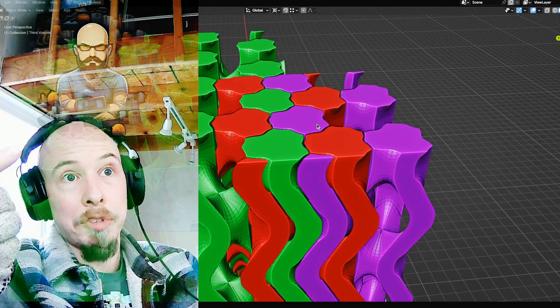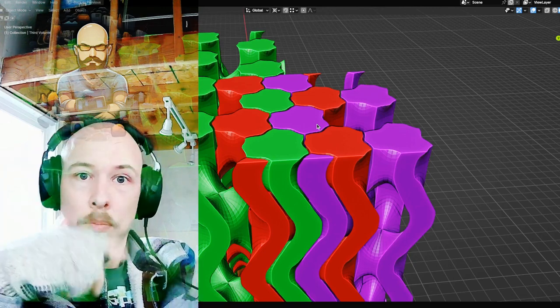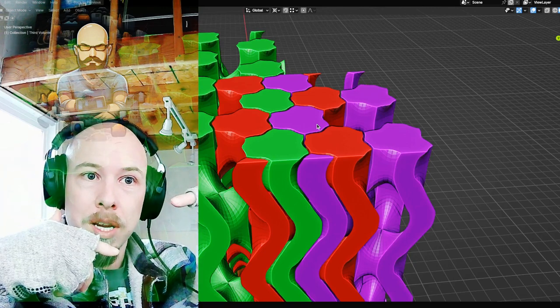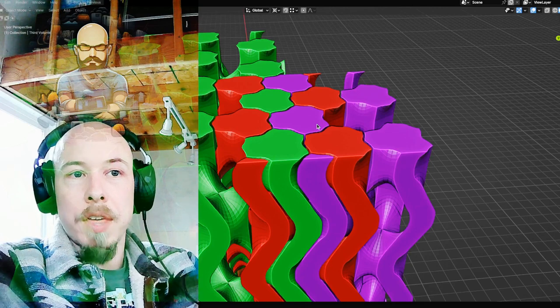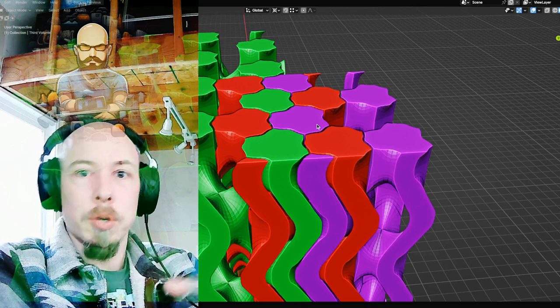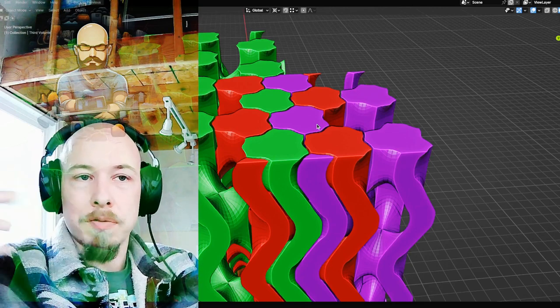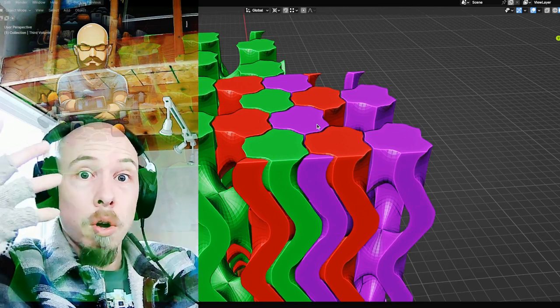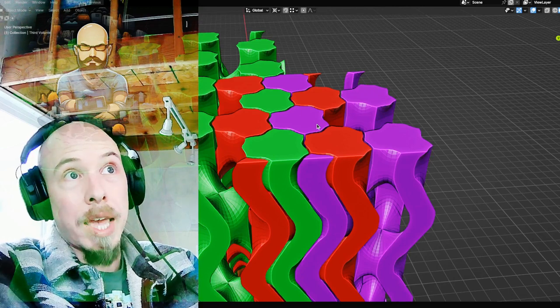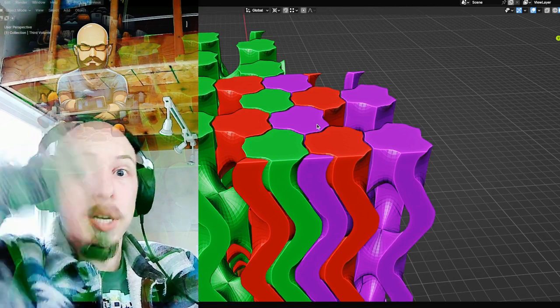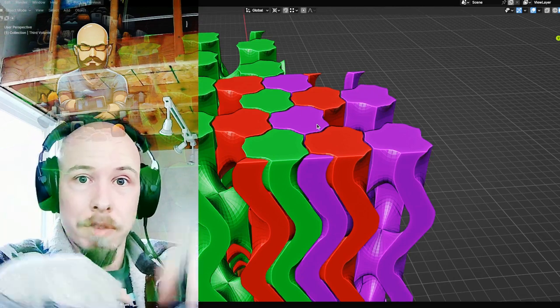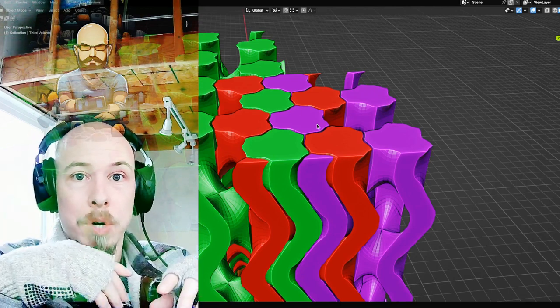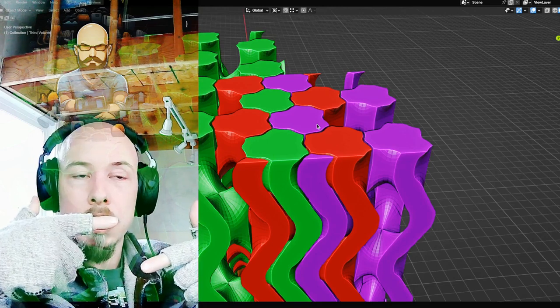You could have like a control fluid and then that you modulate the speed of and then another one that's a process fluid and a third one is a process fluid that are going. You can also have the heat exchanger running and clean one of the volumes. So you take one of the volumes out of production. You've still got two volumes doing heat exchange.